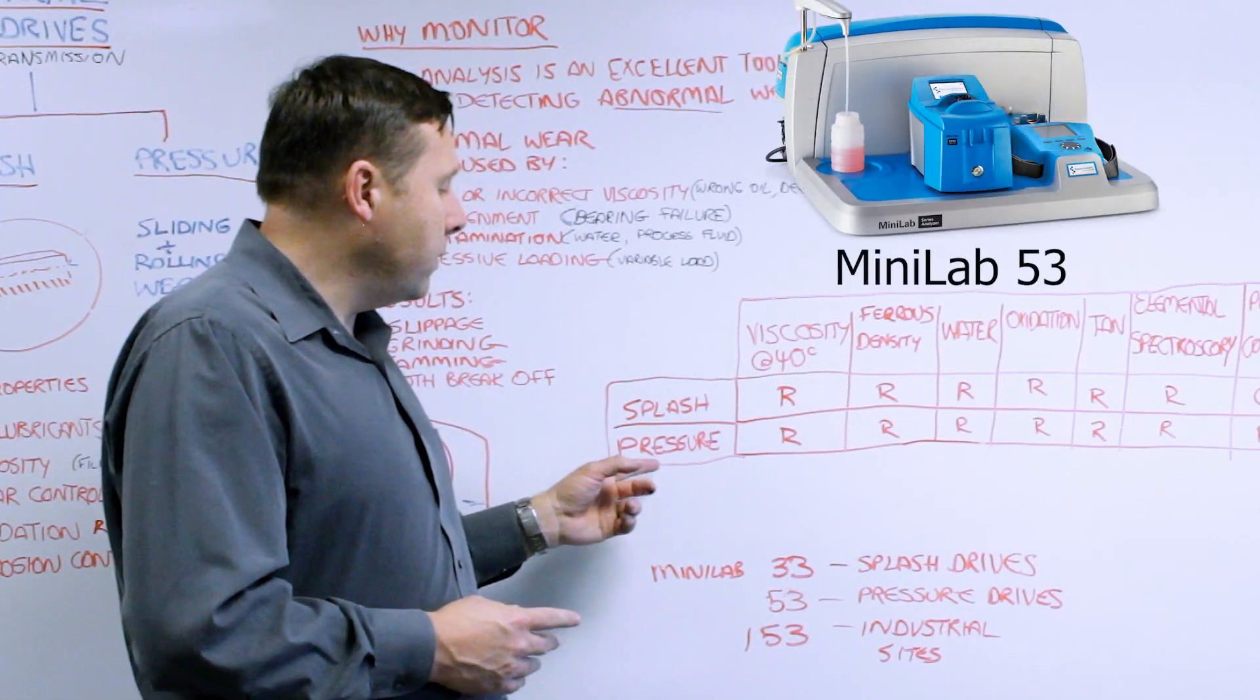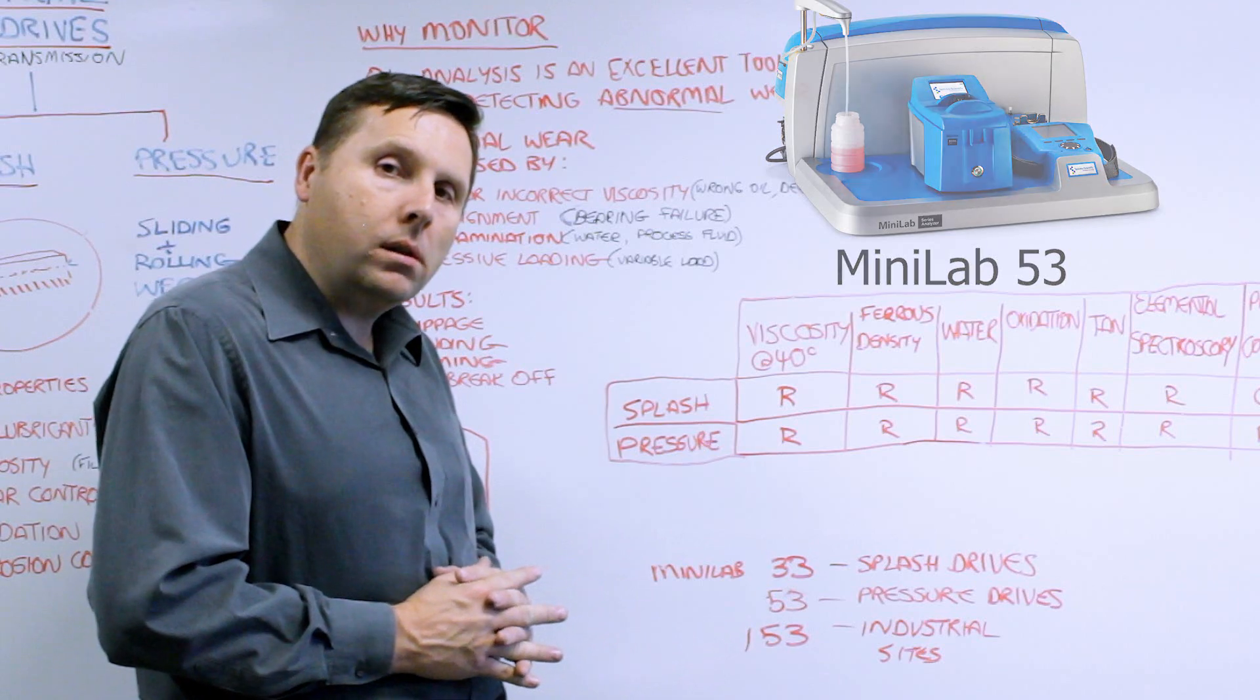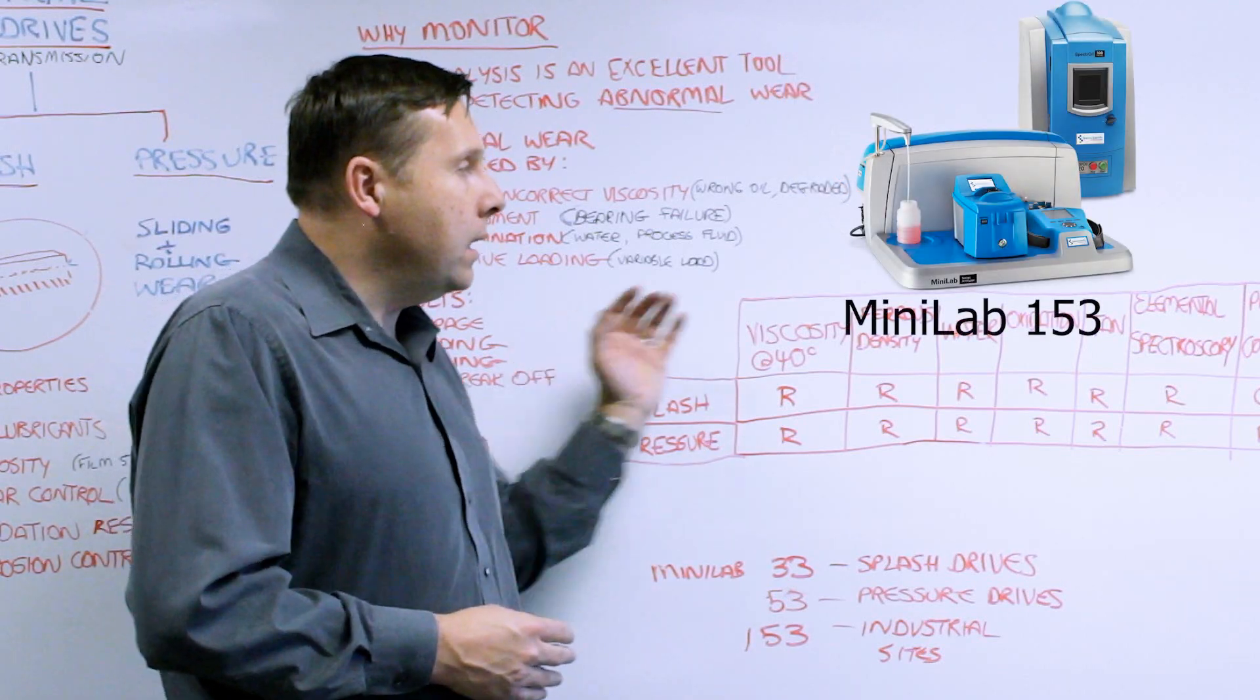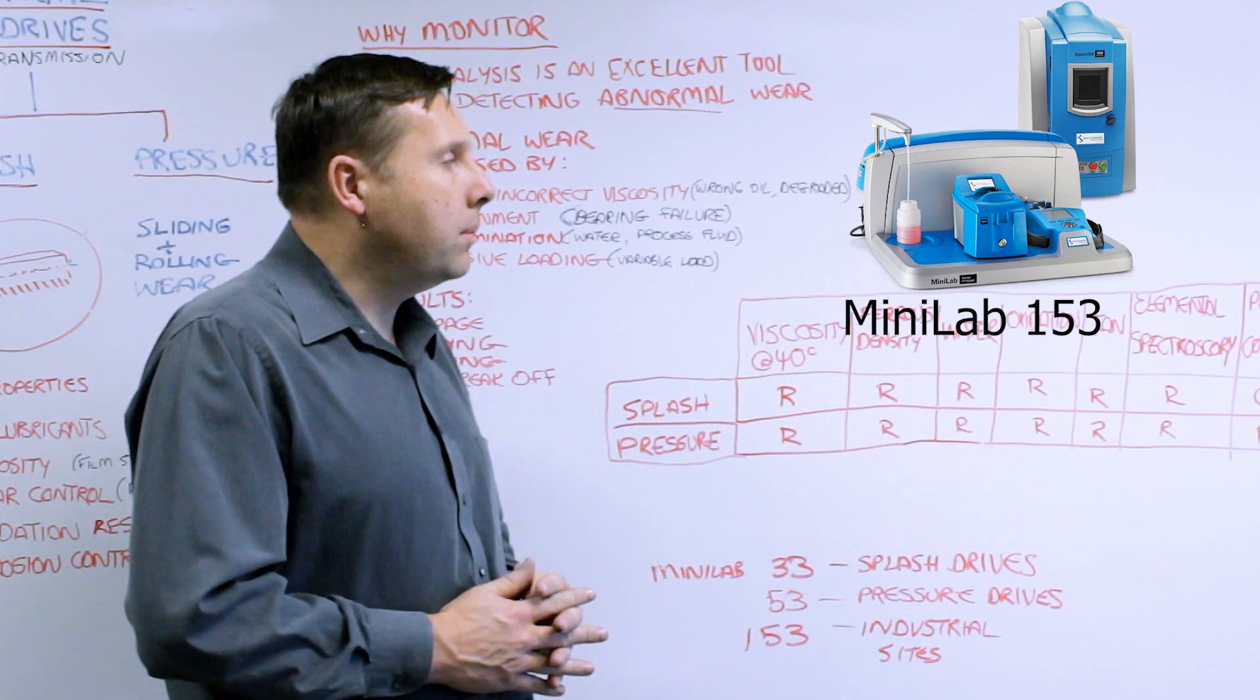The 53 is perfect for pressurized systems because it's got the particle count and the ferrous particle count included. And then the 153 system includes the elemental spectroscopy and it's ideal for all types of industrial systems.